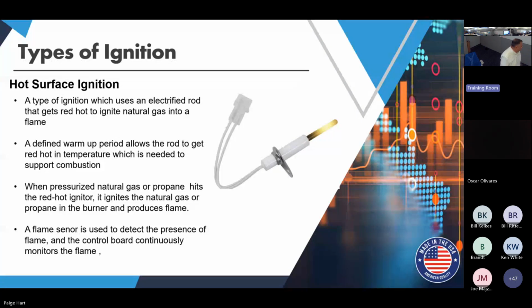So we talked about the flame sensor—that's a basic, general understanding of a hot surface igniter. You'll see these in a lot of boards. They're pretty reliable. Some people say they're a little less reliable than spark ignition because they can burn out, but I don't find that to really be true. I find spark ignition more troublesome because you need a very good ground, and sometimes houses don't have a good ground. On your 3-prong plug you have a hot, a neutral, and a ground—you need that good ground to make good connections with spark ignition.